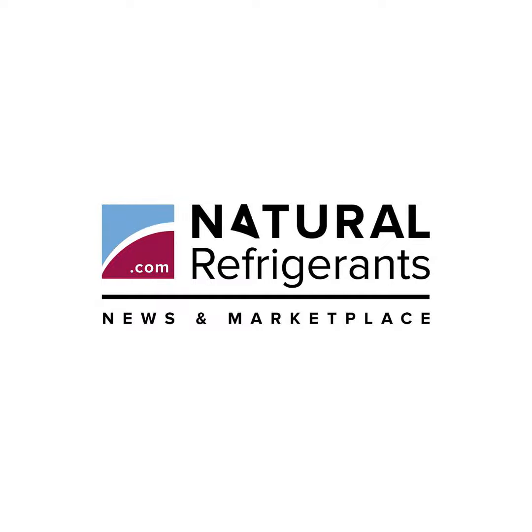New application. Generally, district heating networks with natural refrigerant heat pumps use CO2 or ammonia refrigerant. However, hydrocarbon heat pumps are also starting to be used in such applications. Danish manufacturer Energi has developed a water-to-water 1 megawatt, 284 tons refrigeration, isobutane heat pump to support the subcooling of CO2 heat pumps in district heating networks with high return temperatures. 6 Energi isobutane/propane heat pumps will supply more than 30 megawatts, 8,530 tons of refrigeration of heat to a district heating network in a Finnish city using waste heat from a local data center.